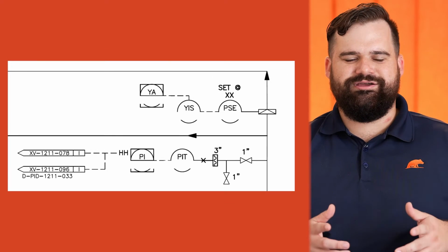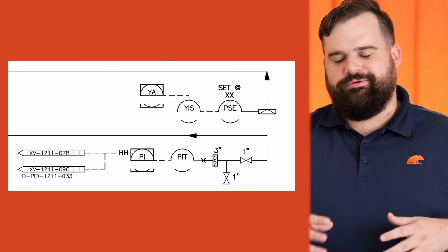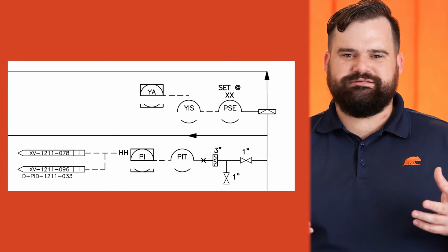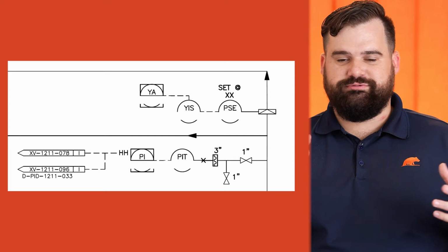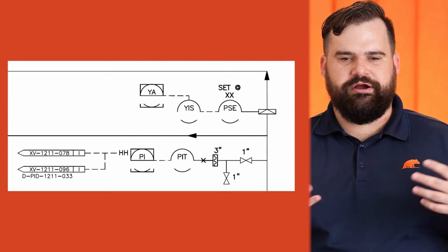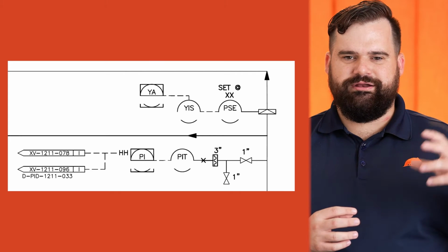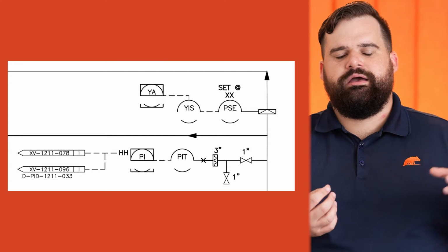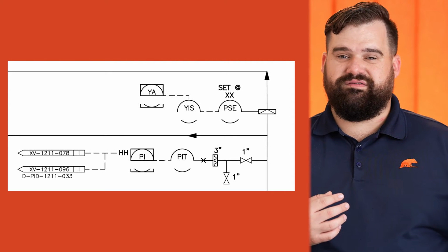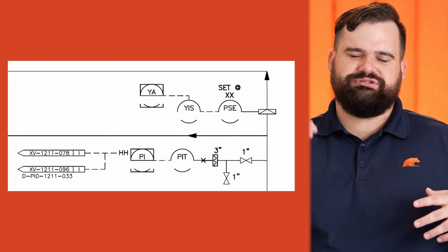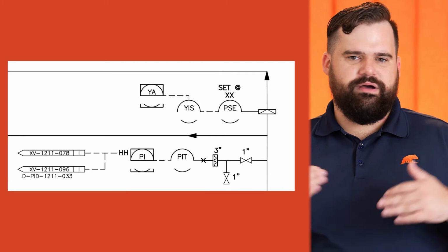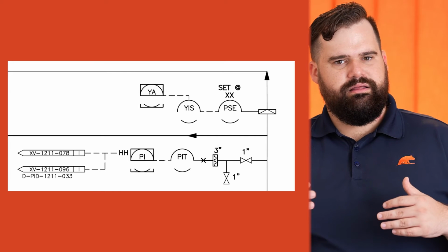Secondly, you can see here, we're talking about layering. So we layered an instrumentation safeguard with a mechanical safeguard, but it still gets the point across, right? We can do this with all safeguards really, but we can do it with multiple instrumentation safeguards as well. So we have a pressure interlock trip. You can see the PIT here, and that's from a transmitter, and then it's going to trip something else in the system, which is also in line with the PSE that's being used. So you can layer both safeguards as long as they're independent together.